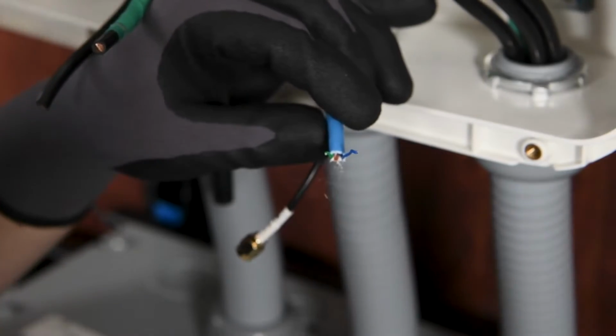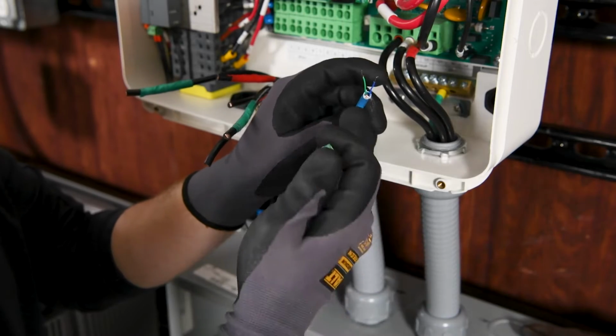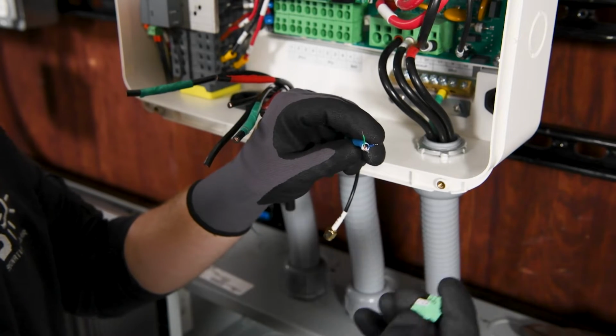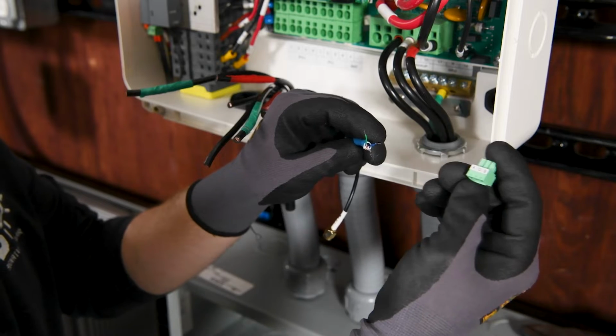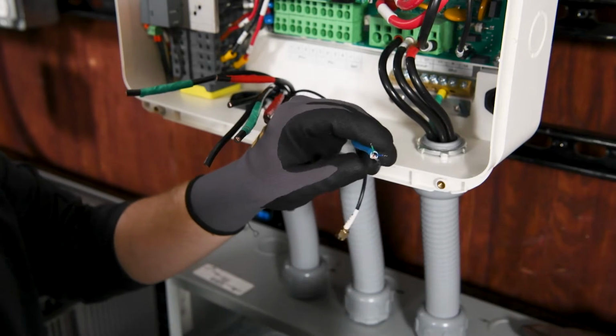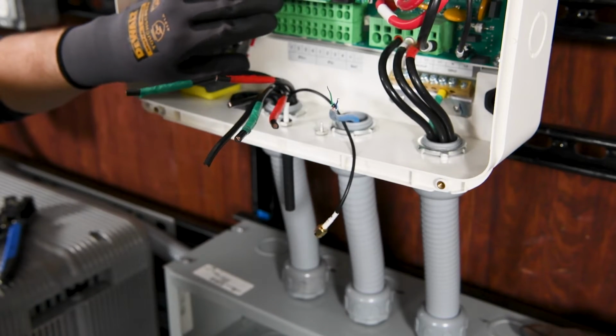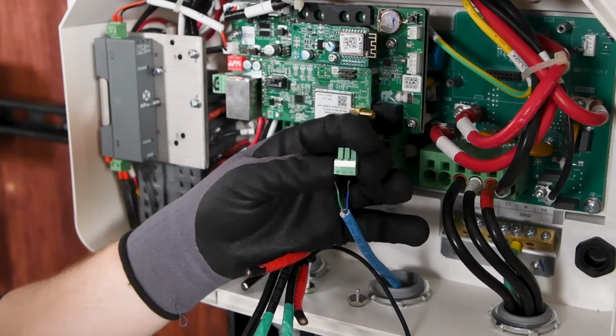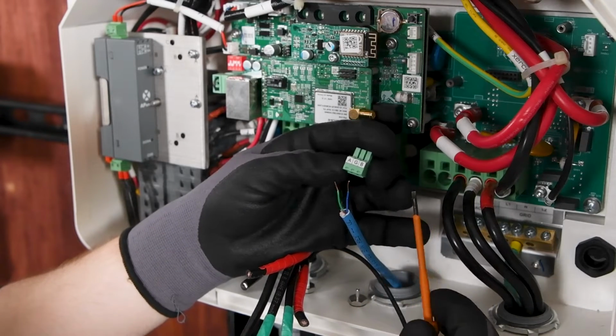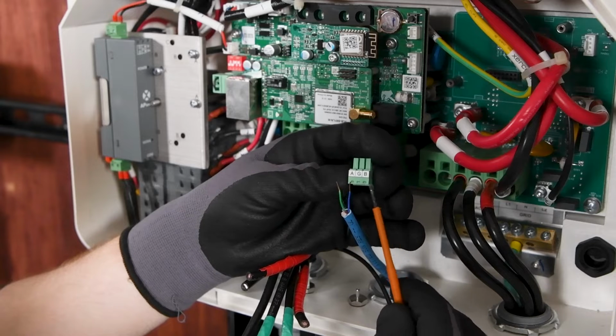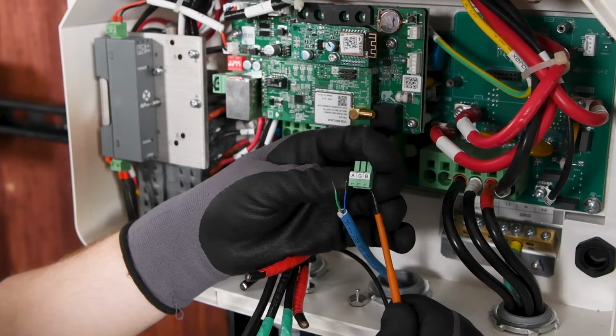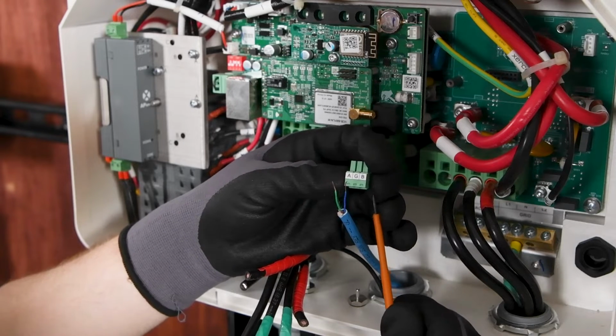Now that we have our blue and green conductors from our Cat5 or Cat6 Ethernet cable, we will be using the 3-pin connector that comes with the Growatt 11.4 inverter, and this will connect over here on the communications board. Setting up our communication cable with our 3-pin connector. Now this 3-pin connector comes with the Growatt 11.4 and all the Growatt inverters.